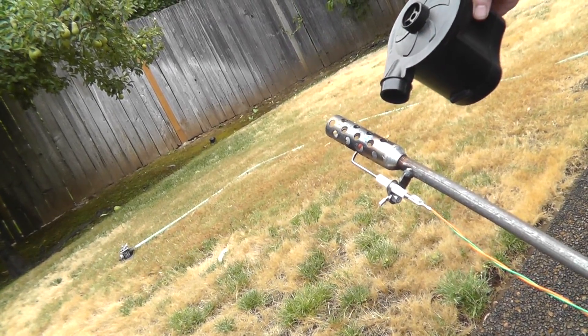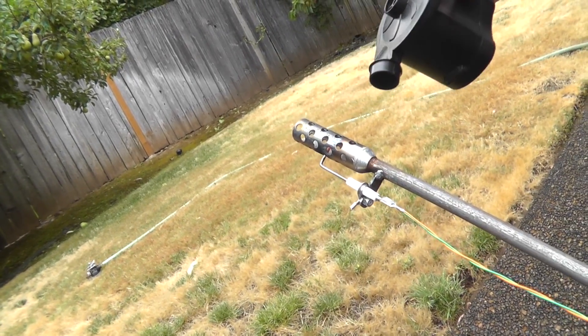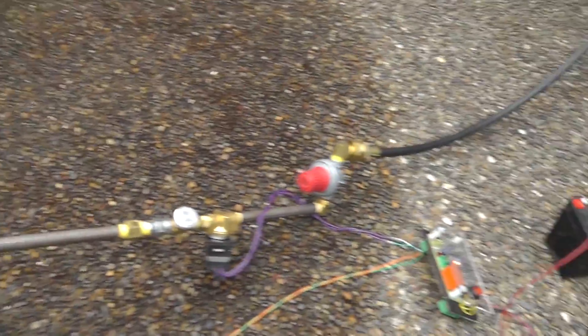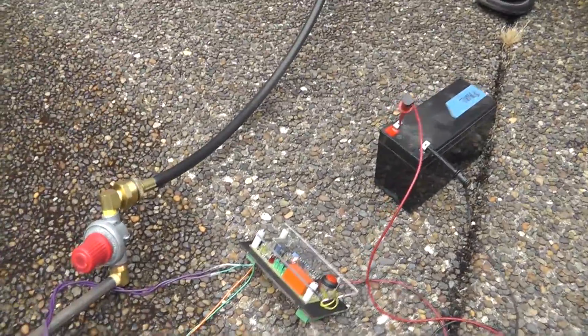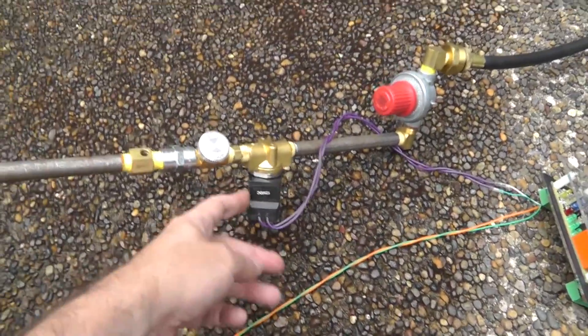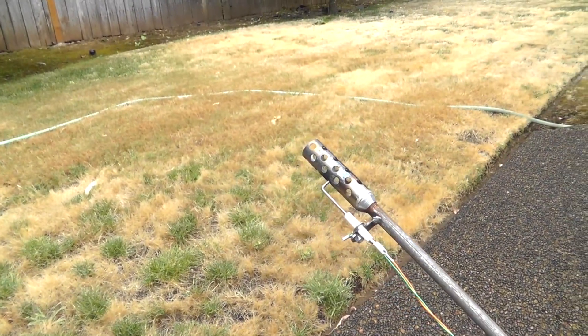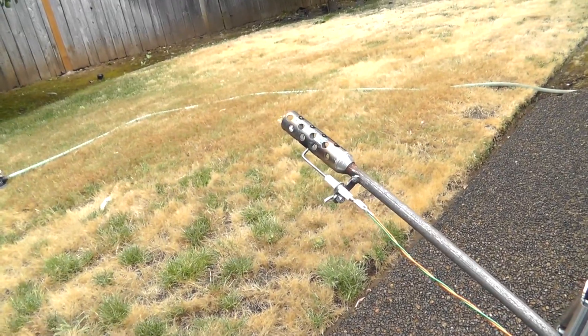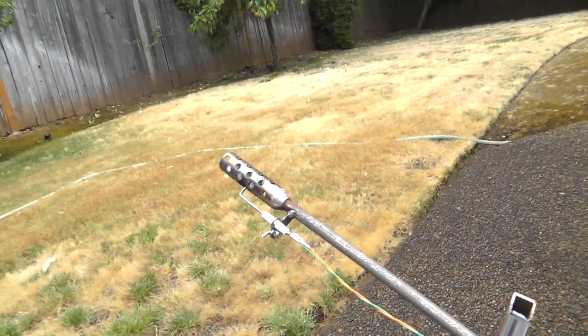We still have fire. And here it turned off the relay — I can feel it. Sure enough, the LEDs are off and it has turned off the gas here at this valve. Now that the gas is off, the fire will not restart until we push the red button or put a flame on it. But now it's stopped.